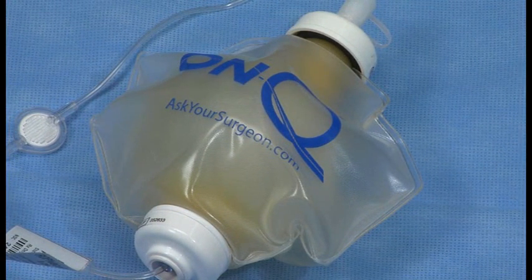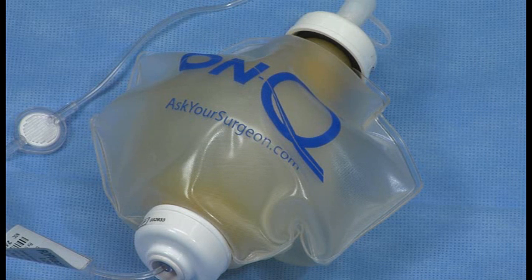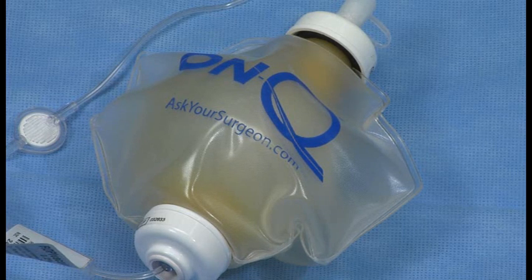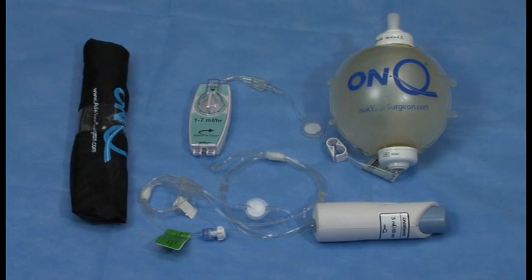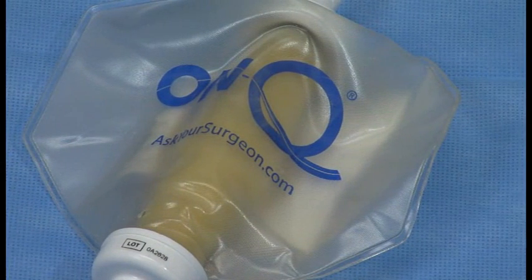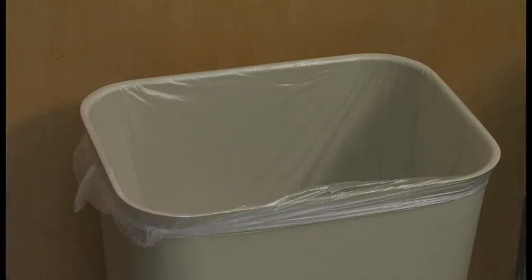Your pump will get smaller over time. It will likely take 36 to 48 hours before you notice any change in size. Initially, you will notice that there is a more wrinkled appearance. Your pump will last 2 to 4 days and is dependent on the type of ON-Q pump selected, the settings, and the on-demand bolus usage, if available. The pump is empty and can be removed when it resembles an apple core and the sides are flattened. The infusion pump and catheter can be thrown away. No special disposal precautions are necessary.